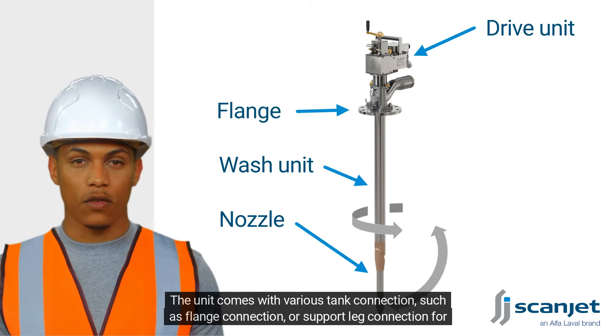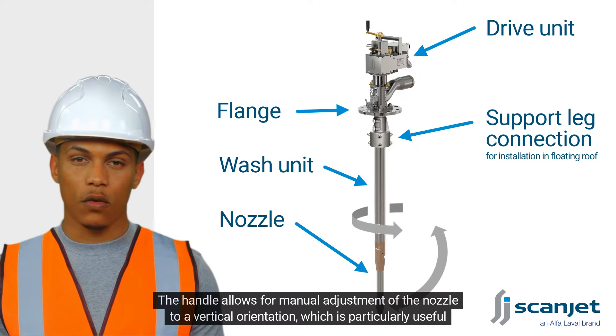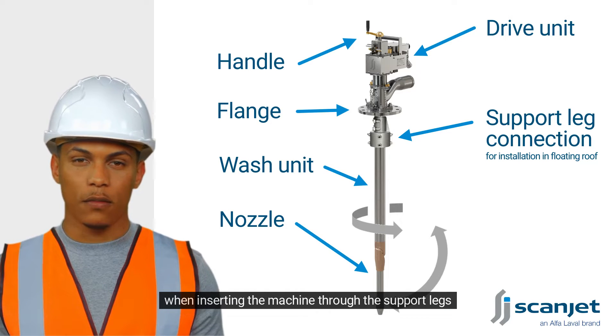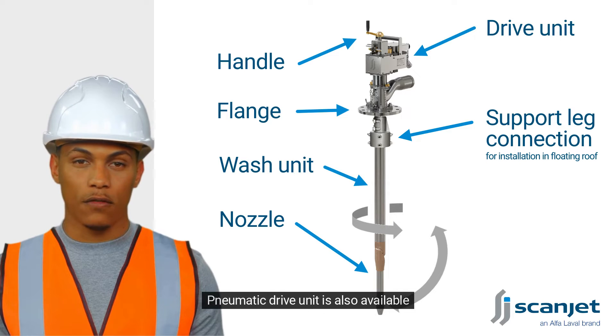The unit comes with various tank connections, such as flange connection or support leg connection, for easy mounting on the floating roof. The handle allows for manual adjustment of the nozzle to a vertical orientation, which is particularly useful when inserting the machine through the support legs. A pneumatic drive unit is also available.